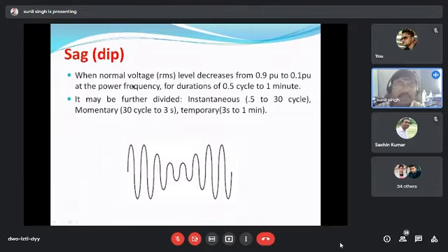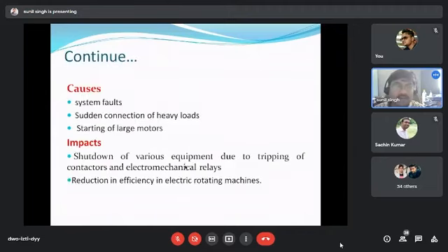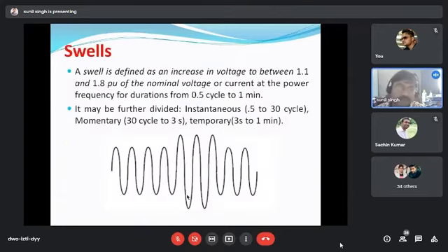So we have also discussed the sag. What is the sag? Simply, a voltage dip of less than 1 minute duration is known as the sag. So what is the cause of sag? The causes of sag and swells are faults. Generally, fault is the main cause of the sag, and sudden connection of a heavy load may also lead to the sag. What is the impact of this sag? This sag may shut down various equipment due to tripping of the contactors and the electromechanical relays. This sag is very important, as a very huge loss in terms of money occurs every year in every country, in our country also.